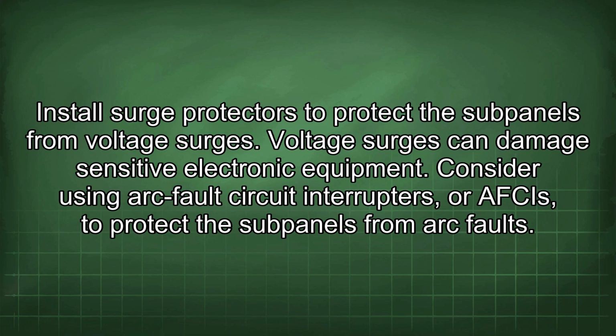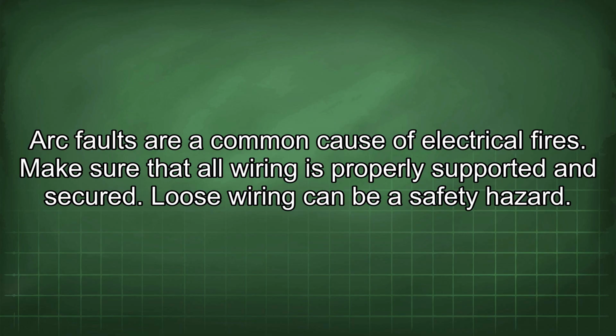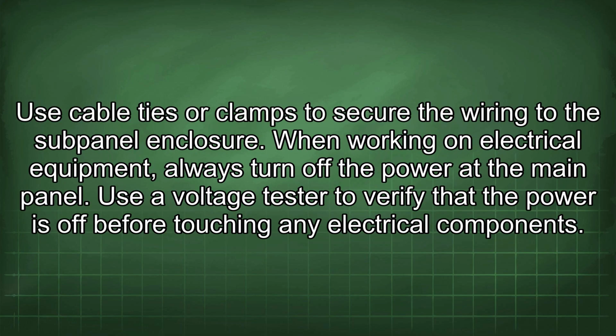Install surge protectors to protect the subpanels from voltage surges. Voltage surges can damage sensitive electronic equipment. Consider using arc fault circuit interrupters, AFCIs, to protect the subpanels from arc faults. Arc faults are a common cause of electrical fires. Make sure that all wiring is properly supported and secured. Loose wiring can be a safety hazard. Use cable ties or clamps to secure the wiring to the subpanel enclosure.